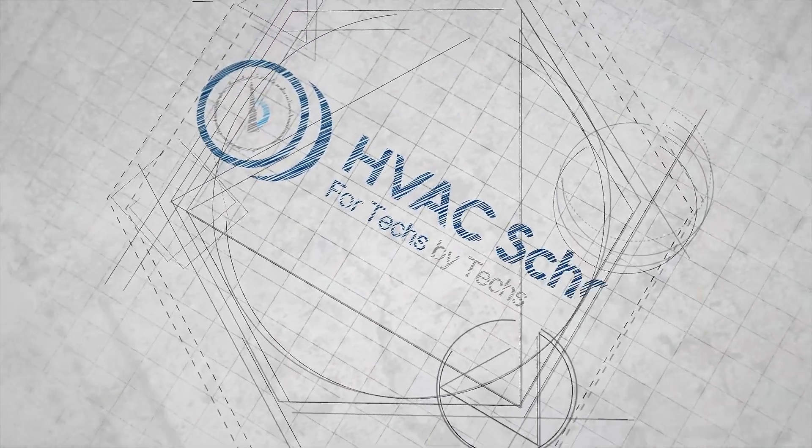Always appreciated when you send in these types of videos that are really just excellent learning opportunities. Jim Bergman, my favorite hot air expert, talking about mass flow rate versus volume flow rate of air. Most technicians don't understand this. Almost all air conditioning, if you look at chapter one of refrigeration technology: Q equals mass times specific heat times delta T.